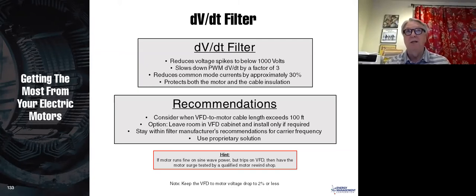And if you don't see any voltages over 1,000 volts, then you don't need a dV/dt filter. If you do see them over 1,000 volts, then you could go back, if you leave room in your VFD cabinet, and add a dV/dt filter. You also want to stay within the manufacturer's recommendations for carrier frequency. We could talk a lot about carrier frequency, and we will, but not today. That'll be in our VFD class.